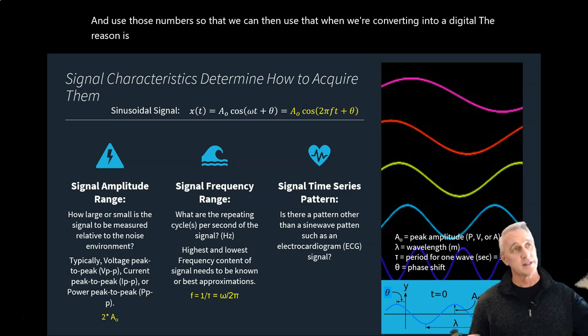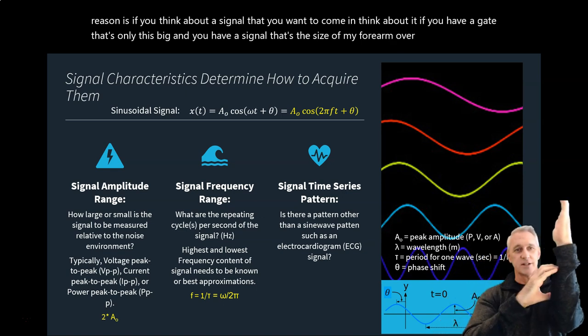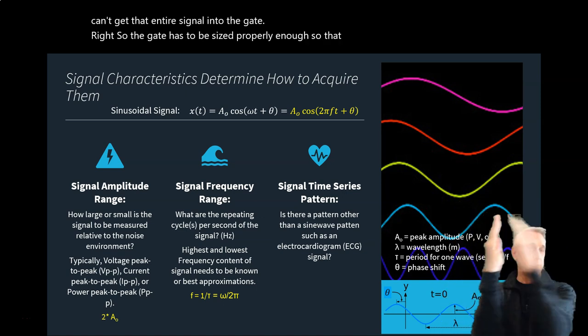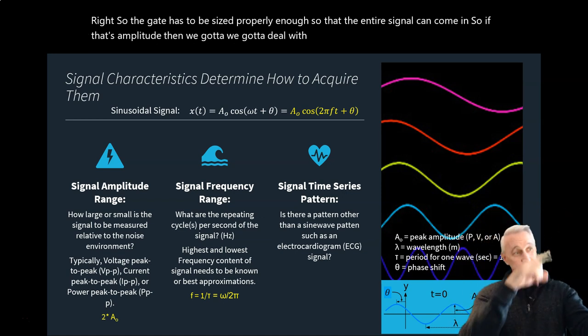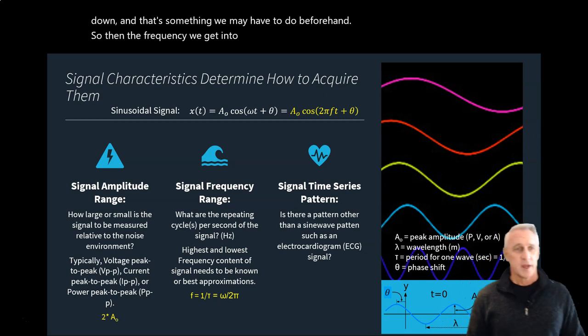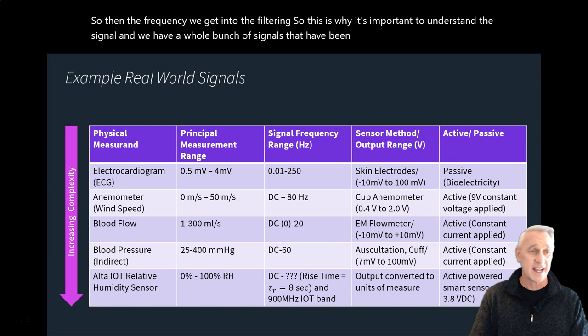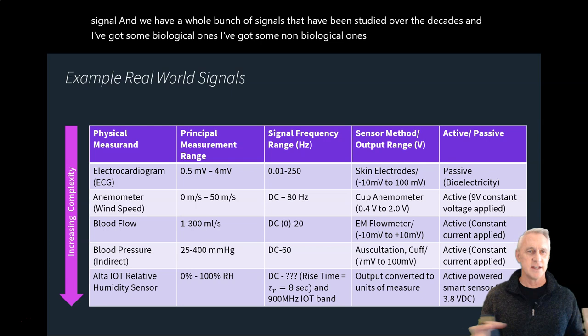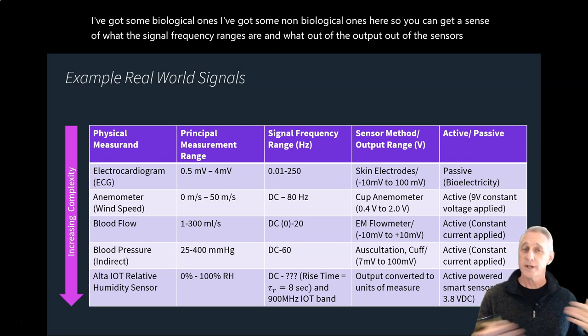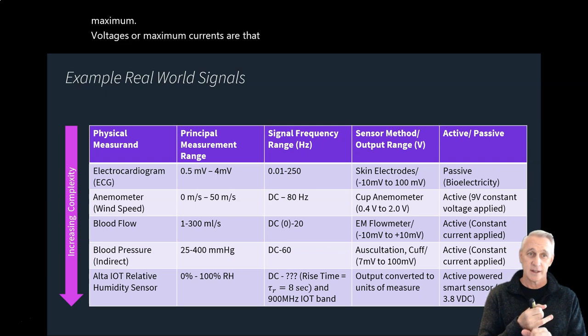Think of it like a gate: if the gate is only so big and your signal is larger, the signal gets clipped. The gate must be sized so the full signal fits through. Similarly, we need to understand the frequency range. For example, an ECG signal ranges from negative 10 mV to 100 mV. When acquiring it, you want your system capable of acquiring 100 mV or more, with a little buffer so the signal isn't cut off.